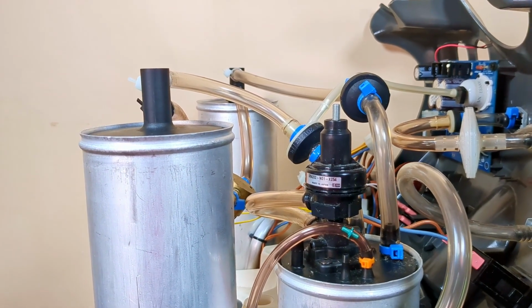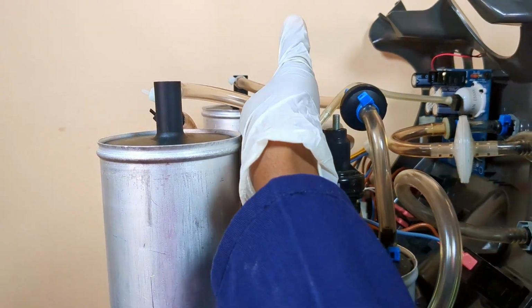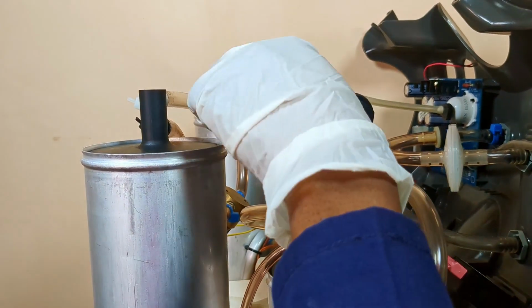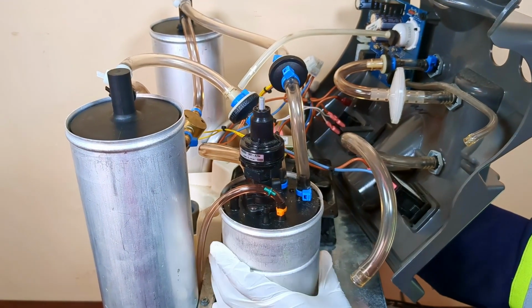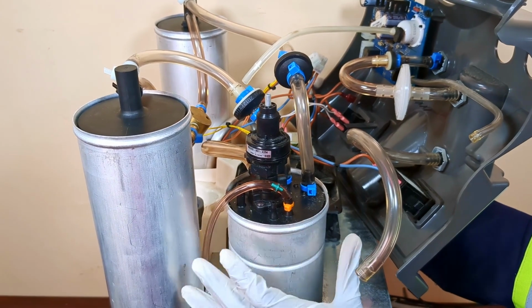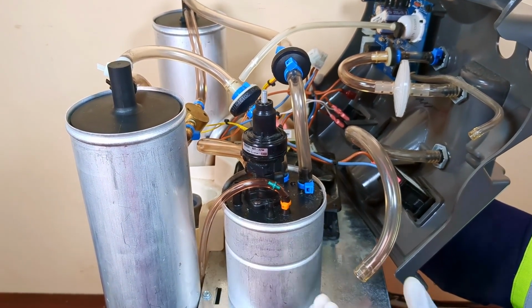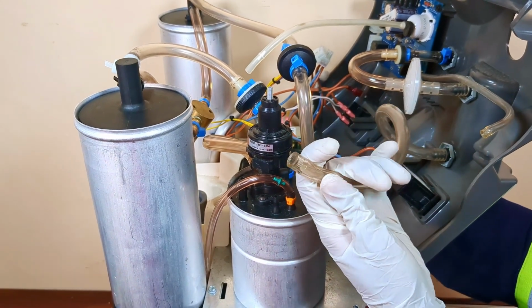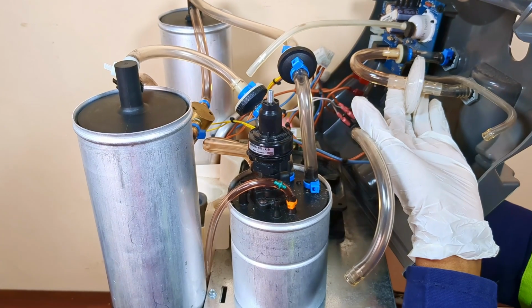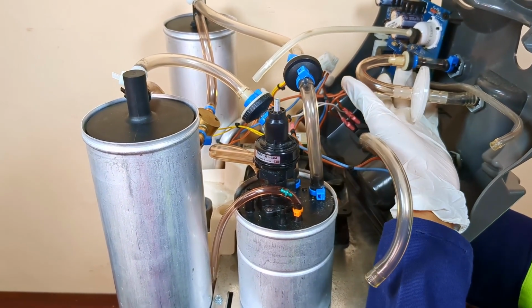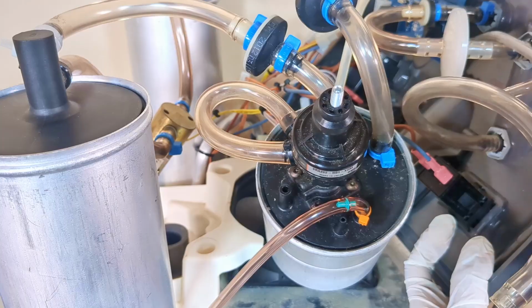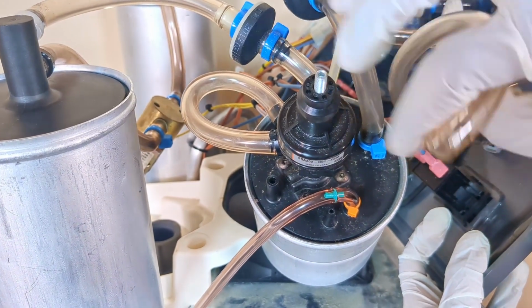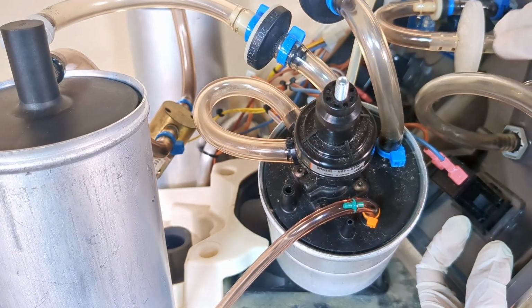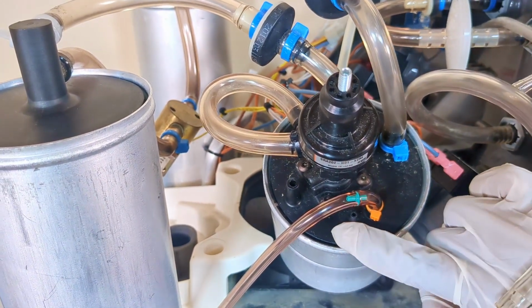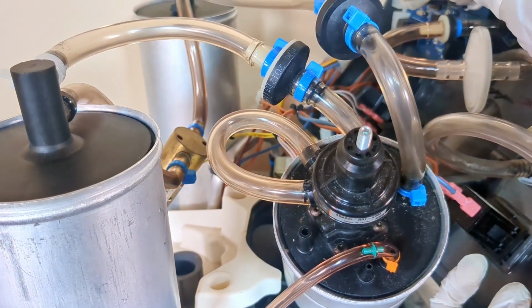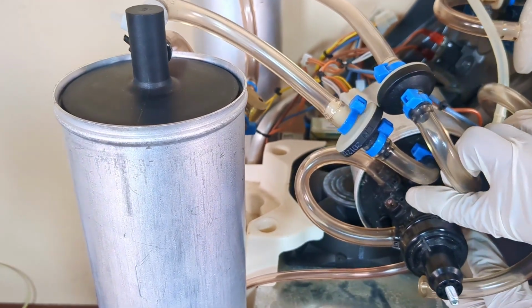Once the oxygen has been separated, it flows from either of the two sieve beds through these two tubings while passing through these one-way valves, and finally moves to the product tank. From there, the air is regulated to a pressure of 5 psi. It then proceeds through this tubing to the flow meter, the outlet HEPA filter, and then finally passing through this check valve before it is delivered to the patient. The tube going to the flow meter is connected to this port. The tube going to the transducer is connected to this port. And finally, the tube going to the oxygen sensor is connected to this port.